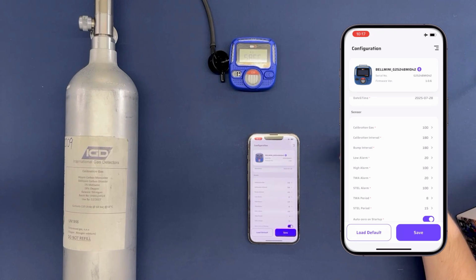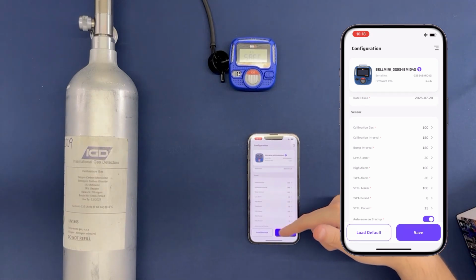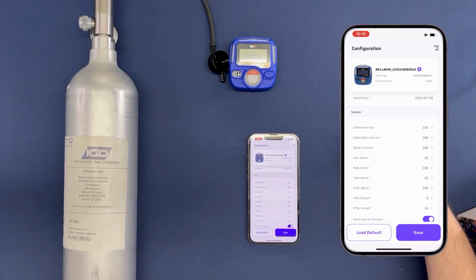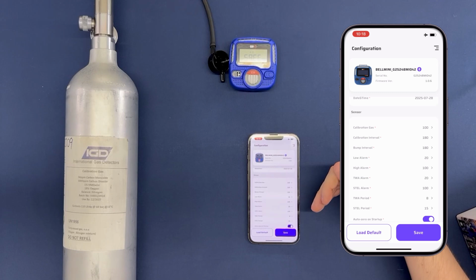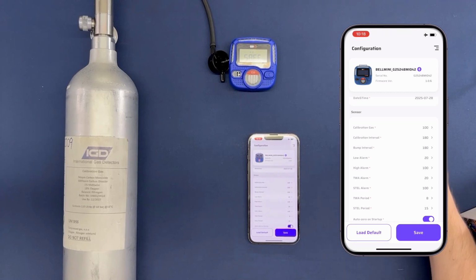One of the other settings I want to point out is the TWA and STEL period, and you can actually change these to match what you're doing on site. So again, as standard, it's 8 hours and 15 minutes, but if you've got workers that are working only 4 hours, you can change the settings here and just press save.